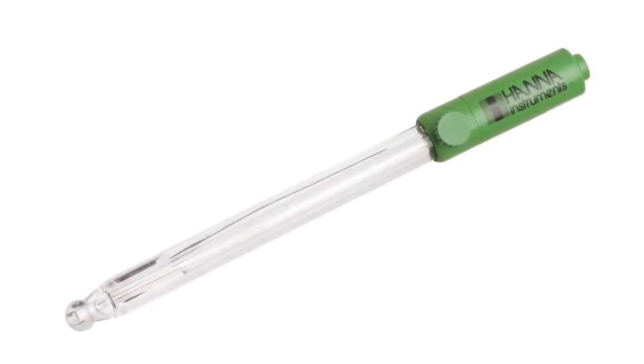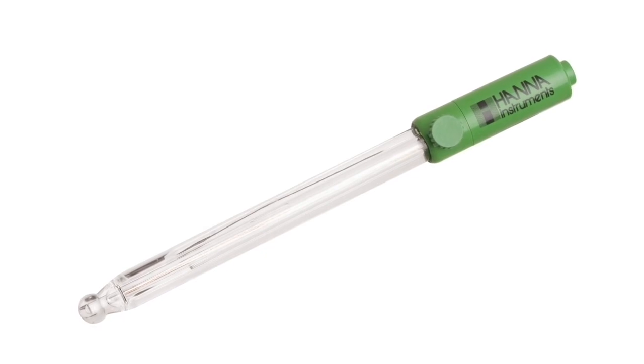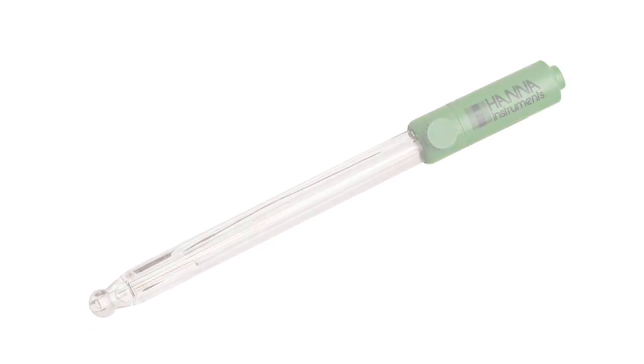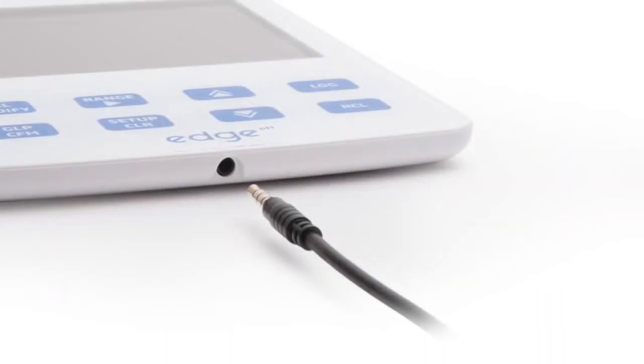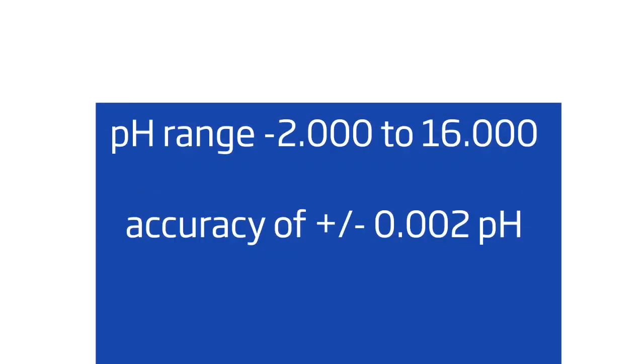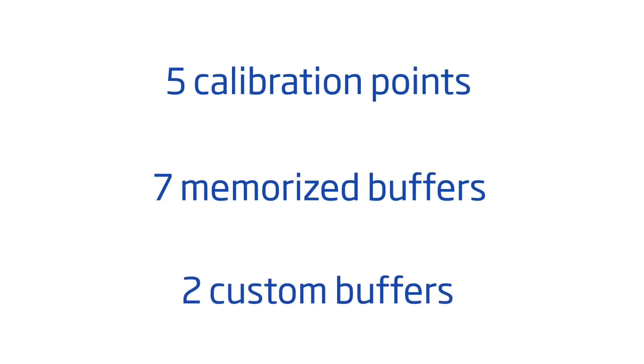The HI11310 is a digital pH electrode with a built-in temperature sensor that connects to edge via a 3.5mm connector. The resolution of the pH range is selectable up to 0.001 and is extremely accurate. Calibration can be performed up to 5 points with a choice of 7 memorized buffers and 2 custom buffers.